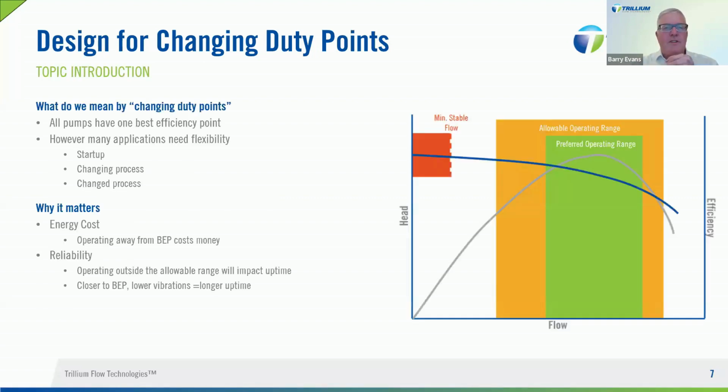So if we go into the pump, what we're showing here is a typical HQ or head flow curve for a pump. And the selection of the pump, from a pump company's perspective, is optimized to ensure stable operation or a performance envelope for the given duty, and includes an optimum and preferred operating range. Obviously, it's desirable for the operation to stay within the envelope and corresponding maximum efficiency points. However, for reasons previously suggested and system changes, this may not always be the case.